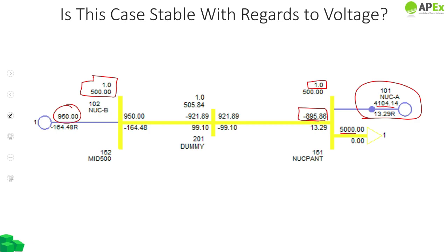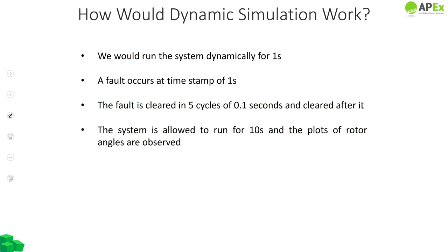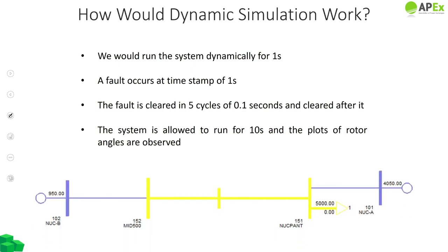Okay, but now comes the main question: is this system stable? In order to check the stability, we will have to run a dynamic simulation. And how would this dynamic simulation work? Okay, firstly, we will run this system smoothly without applying any disturbance for 1 second. Okay, when a time of 1 second is reached, we will apply a fault at this bus. Okay, and this fault would be cleared in 5 cycles, which translates to 0.1 seconds, which is a standard time for clearance of a fault. And once this fault is cleared, we will run the system for 10 seconds to see if the system stabilizes.